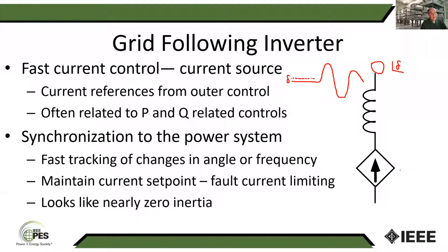the internal angle, so this is basically looking like a current regulated voltage source. The angle of the converter voltage is going to follow this swing, and it's going to maintain a constant angle difference relative to the power system so that it can continue to supply constant power. So if it's in this grid following mode, it doesn't care if there's a power swing. It's going to try to maintain constant power the whole time. And if the power system frequency moves around at the same time this angle is changing, it's going to follow that. From the point of view of someone who gets paid based on how many kilowatt hours or megawatt hours you supply the power system, this is a good way to control it.